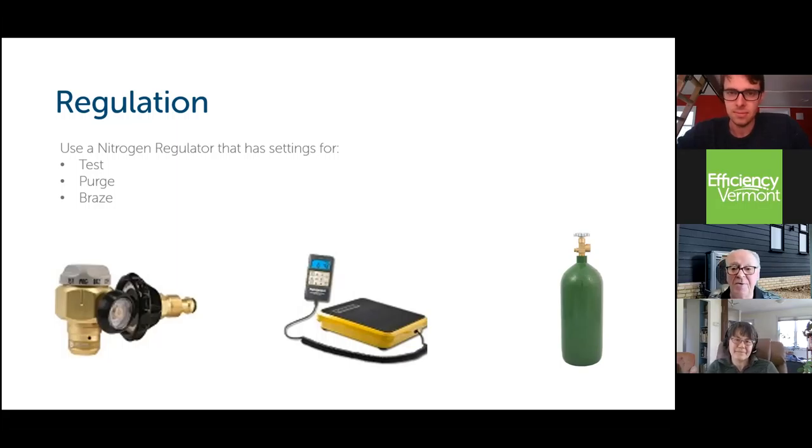Actually, 350 PSIG with a digital gauge, so you're watching very carefully, and even a Bourdon tube gauge, if you're watching, taking a little bit more time, will tell you if you have a leak. We also have to be careful about overpressurizing systems. I mean, even the ductless splits that are out there, the install manual is recommending 600 PSIG. If you look on the nameplate of the equipment, typically if you're doing a new install, you're only pressurizing the low side of the system, the line set and the low side of the system. And if you look at the recommendations stamped on the system, it will not be above 350 PSIG. 600 PSIG may be good for line sets if they're quality copper line sets, but I would stay with 350 PSIG.